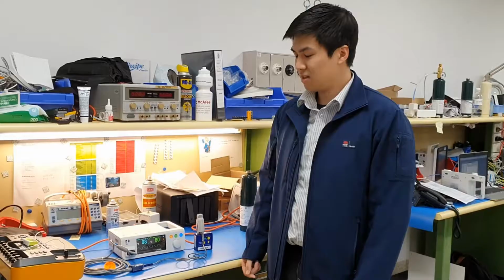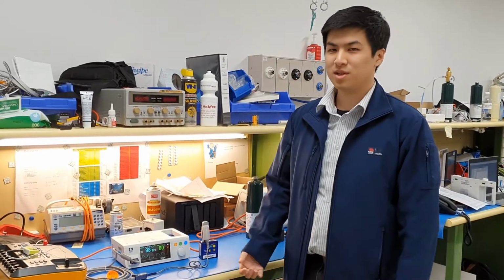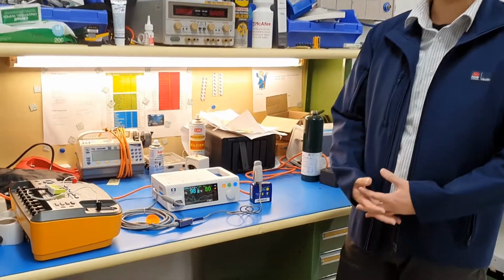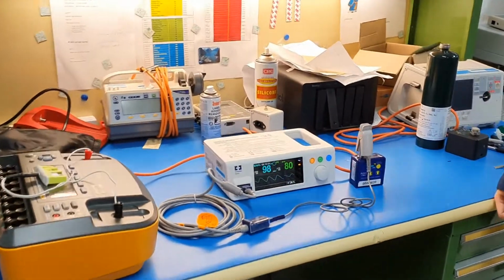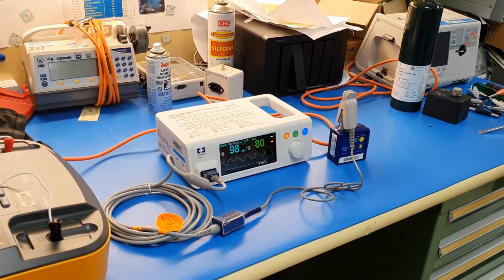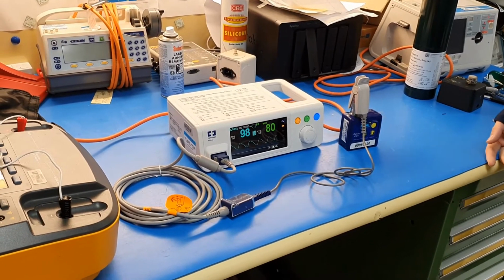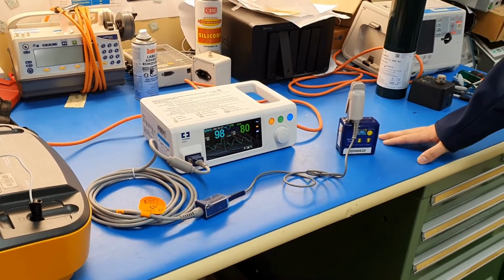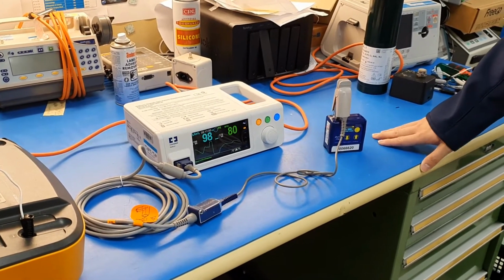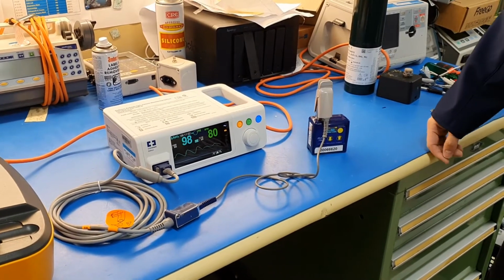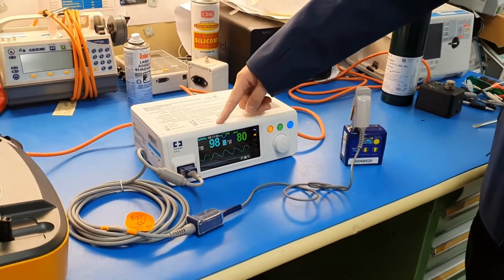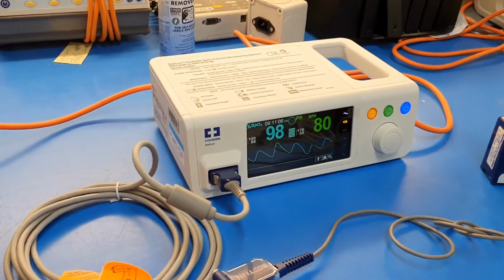Compressions. So here we have a pulse oximeter, which measures our oxygen saturation, or how much oxygen is absorbed in our blood. And here we're doing a test where we just need to show that it's within calibration. So in our simulator we have 98% of oxygen saturation and 80 beats per minute for the heart rate. And as you can see, that it's well within calibration.